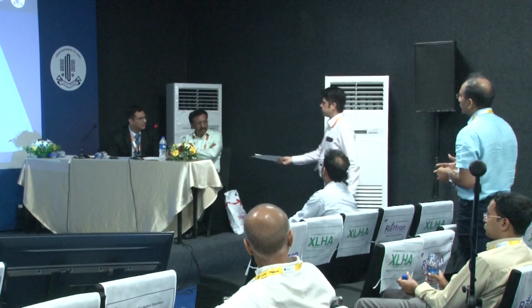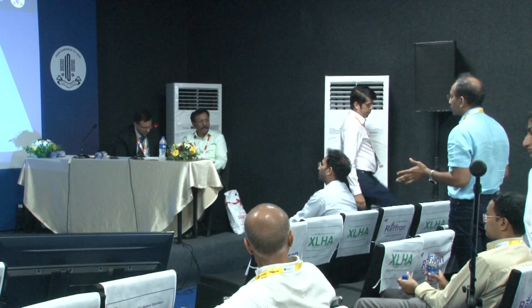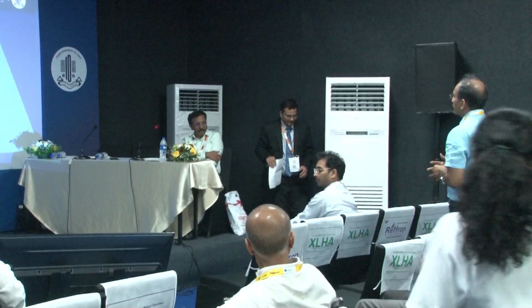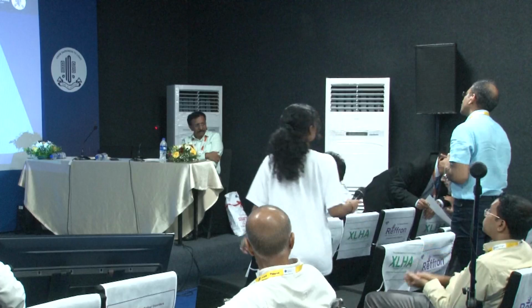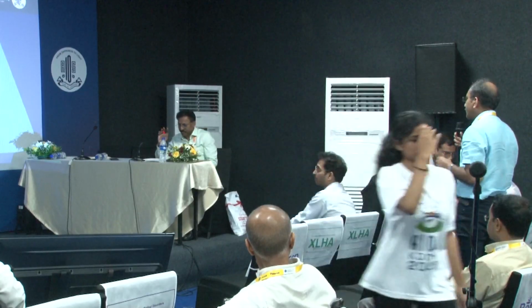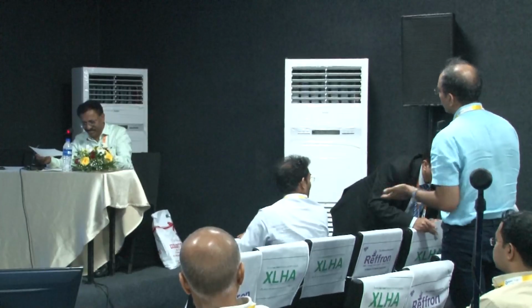You are discussing it for ECU, but when there's a small entrepreneur with a small hospital applying for entry level, what I believe is that a split air conditioner is allowed in an entry level operation theatre. Second thing is in the zoning part, the door: according to the OT consultant, if it is 3 feet, then a single leaf door will be okay. We don't need a 2 leaf door. Right? And other thing is that in the unidirectional flow, when the sterile equipment is taken from the main door inside the operation theatre, and the unsterile material, can it pass through the magnetic pass box to the biomedical waste corridor built outside the operation theatre?